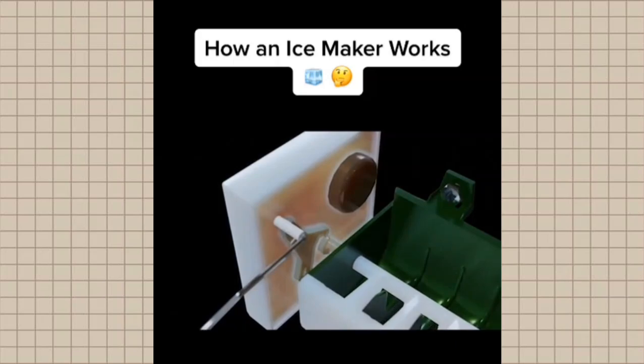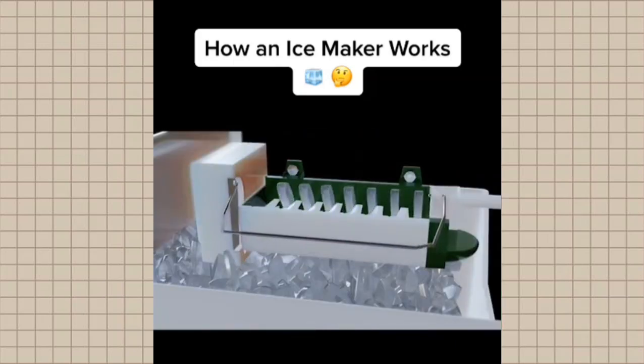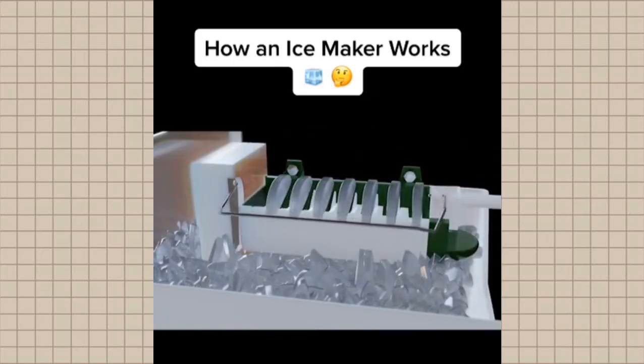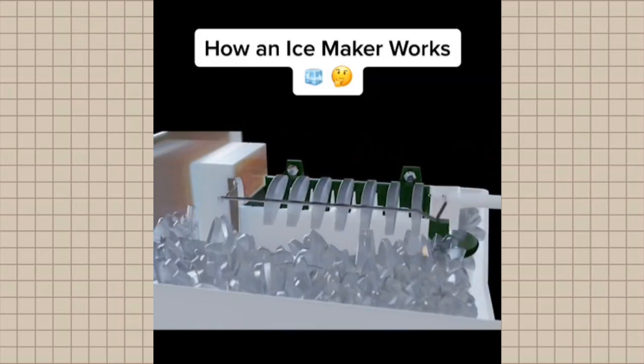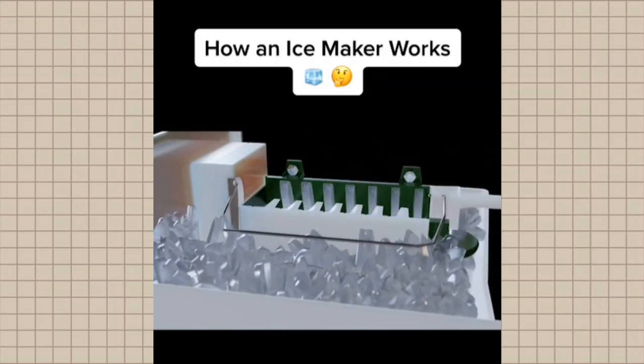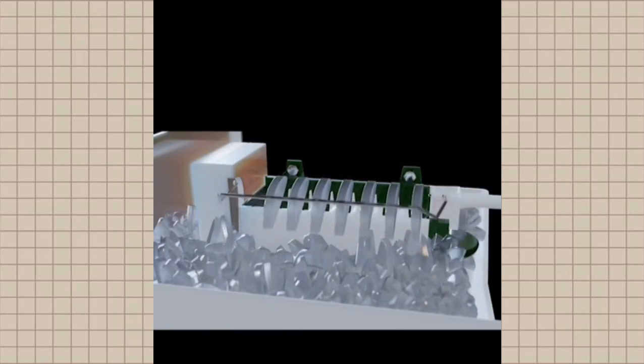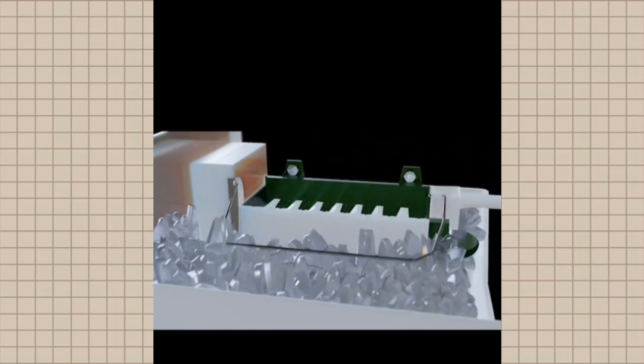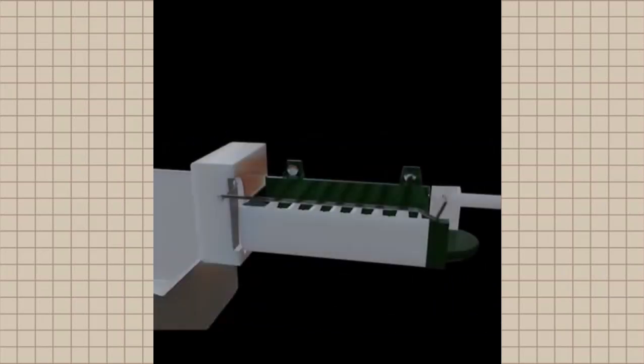At the same time as it's doing the rotation, an arm will be raised and lowered to determine the ice level in the bucket. If the arm raises and comes down and can't move into its normal position because the bin is full, it will turn the ice maker off. Once the ice is used, the arm will go into its normal position and the cycle will begin again once more.